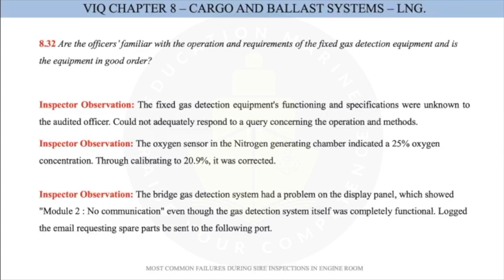And third one, the bridge gas detection system had a problem on the display panel, which showed Module 2: No communication, even though the gas detection system itself was completely functional. So it's logged, the email requesting spare parts to send to the following port. So again, it was some communication error, spare parts ordered, and they will be received. So okay, he wrote this observation, but you are covered. You have what you can do. You order spare parts and it will be rectified as soon as possible once they are received.